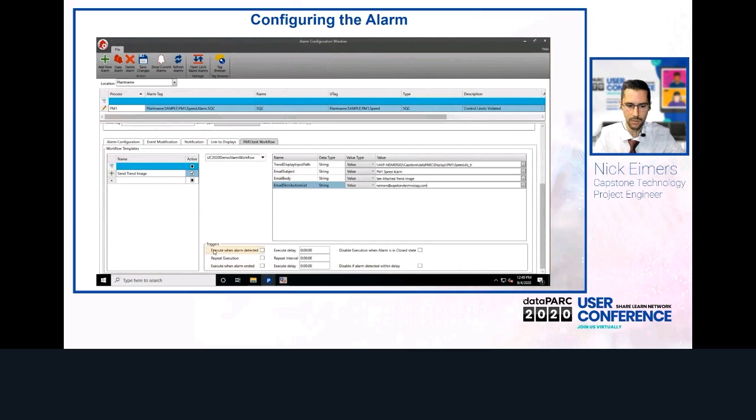A little bit painful. Slow this down just a little bit. You do have to, per PARCtask standards, and how our alarm config for emails used to work, make sure that if you're passing in an email list, it's a semicolon delimited list. So if you were adding more than one person, basically it needs to be email address number 1, semicolon, email address number 2, and so on and so forth.